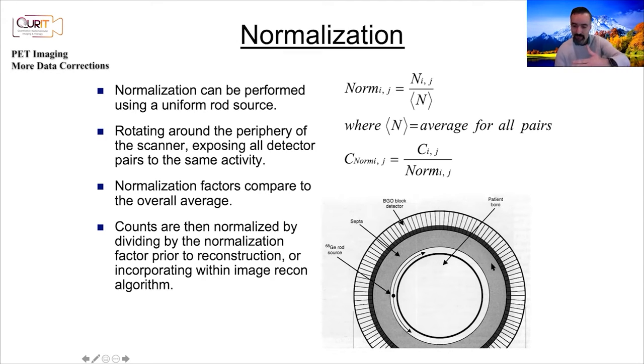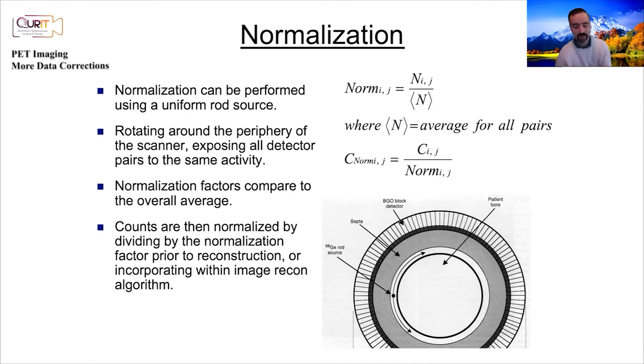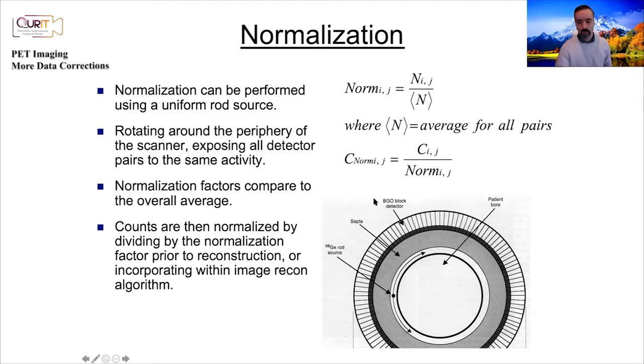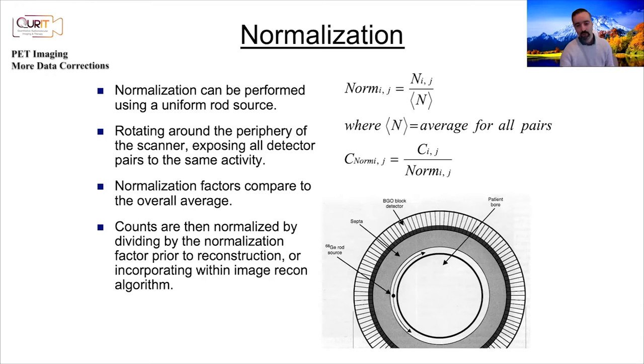By doing this measurement, ideally everything should be uniform but it's not — the crystals vary, and sensitivity changes with angle of entry. It used to be a very long acquisition where you look at all possible lines of response and count how many counts you're measuring. You calculate the normalization for all detector pairs, then when you do an actual PET scan you can correct for each line of response, similar to attenuation correction.